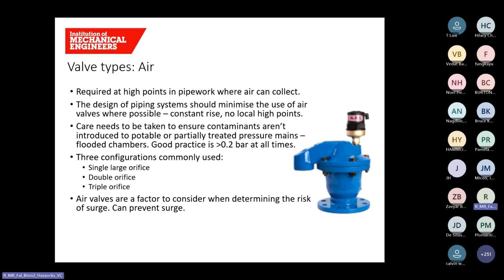There's 3 types of air valves that we commonly use, and these are the single large orifice air valve, double orifice, and the triple orifice. Air valves can also be used to minimise the risk of surge. So when you've got a surge event, an air valve can be used to allow air into the system and relieve the negative pressure.